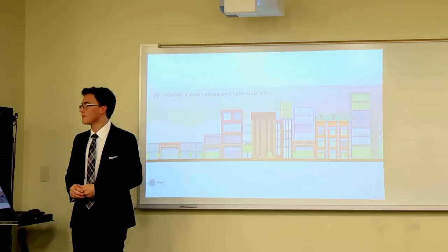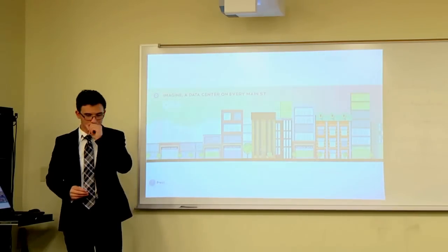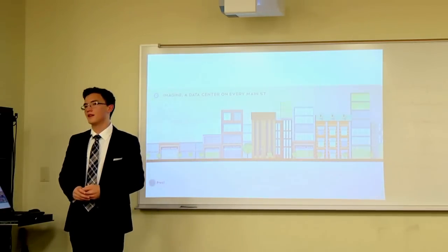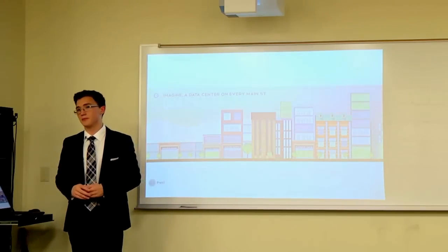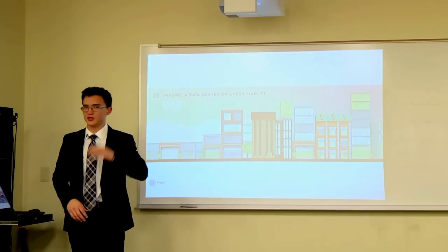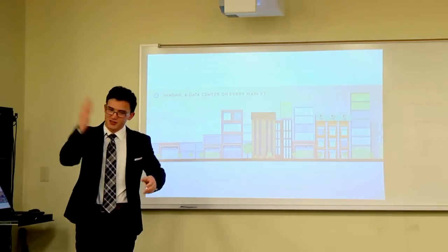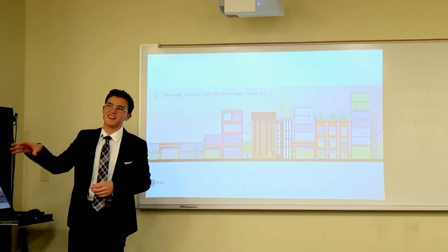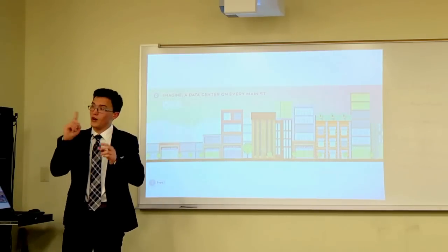How does the energy efficiency compare between a large data center, with X computing power, versus a bunch of smaller ones with the same power? Okay, so what you use is called the power usage effectiveness, PUE, and that basically says you get this amount of power to crunch numbers divided by this amount of power in kilowatts or megawatts that is coming into the building. And the idea is to get as close to 1 as possible.